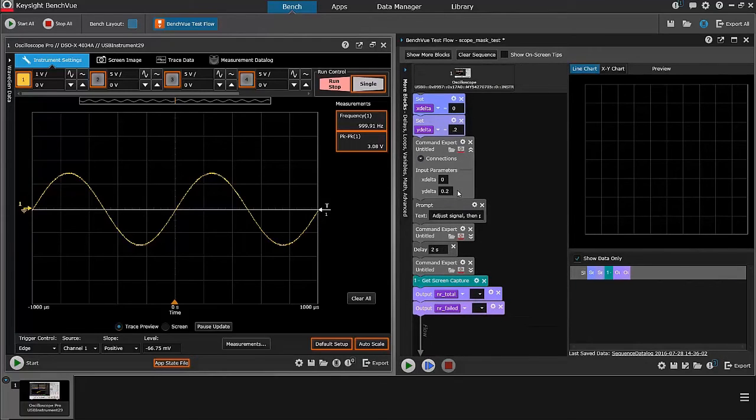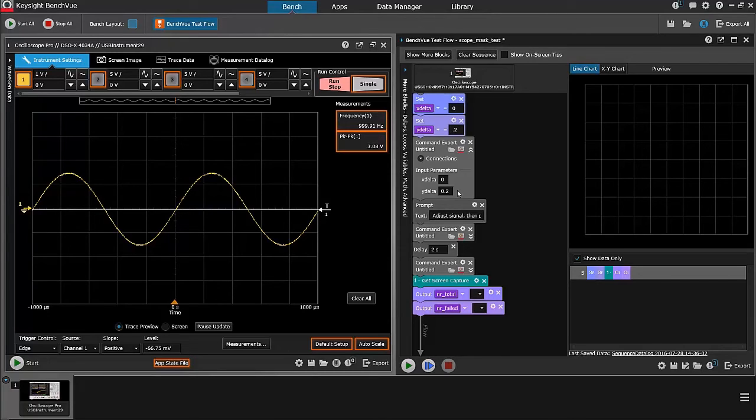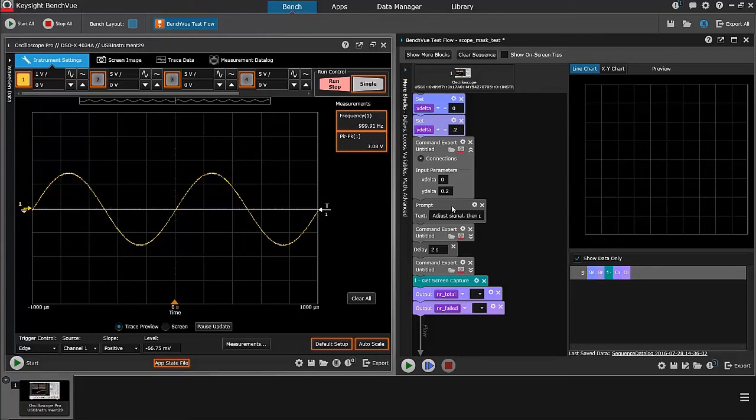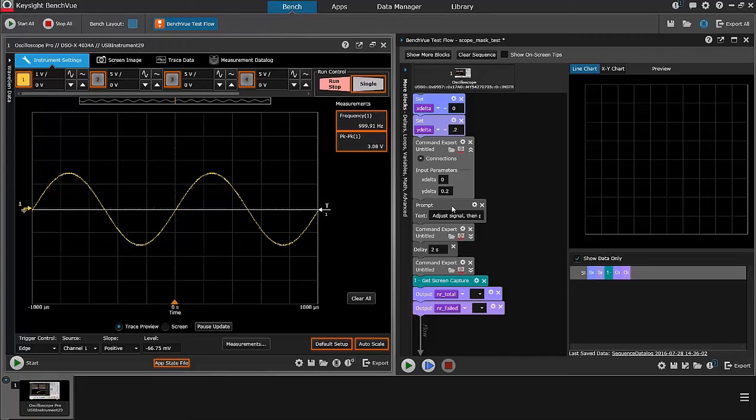All right, so at the end of this first command block, I've got the instrument set up to do a mask test. What I want to do then is apply a signal that's different. At that point, I will change the voltage intensity of the signal going in so that it will generate a failure.